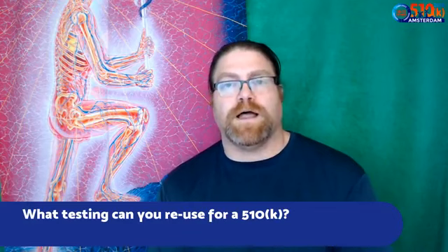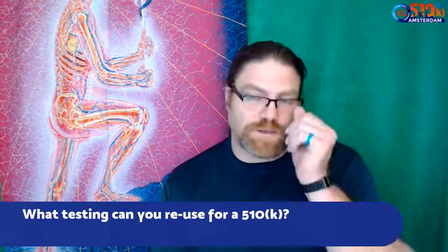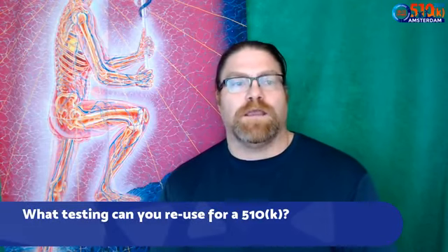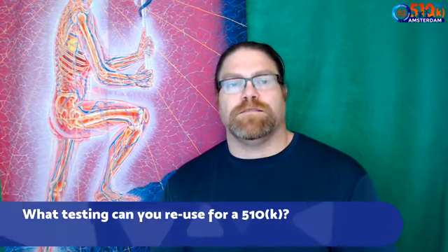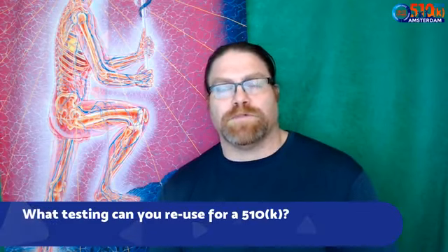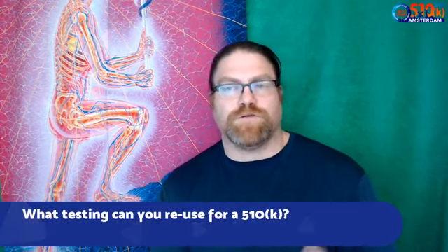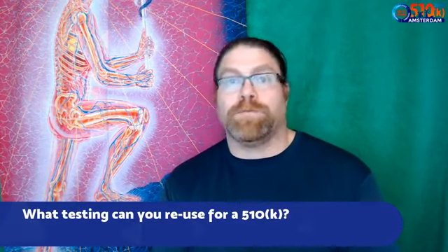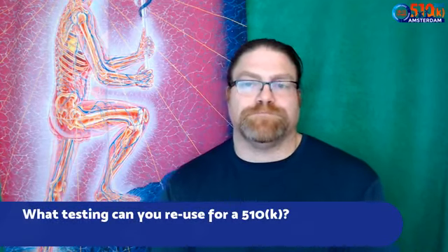So there are some transition differences depending on what regulation or what standard is being applied and what the date is of the implementation, and it changes from country to country. So you need to make sure that you're current with what the US requires. And sometimes I'll find companies will say, "Oh, we're all set. When we go to market our product in the US, we'll just submit what we did in Europe." But between the time that they had done the testing and the time they plan to market the product in the US, the standards will change. And so you have to be compliant with the version of standard that is recognized at the time of submission. Whereas in Europe, you have to be compliant on an ongoing basis and have to update your testing if the standards are updated.